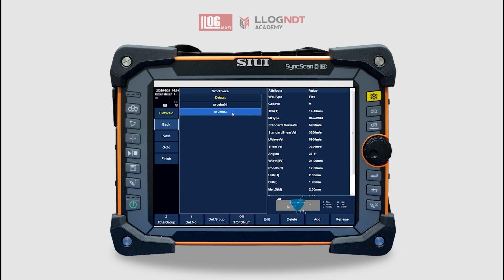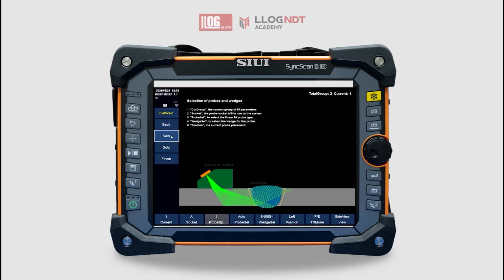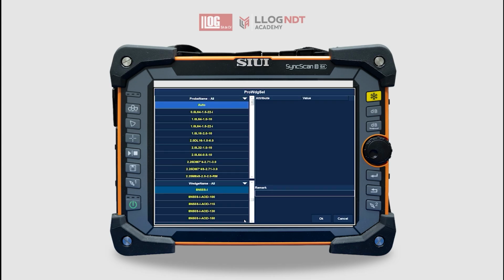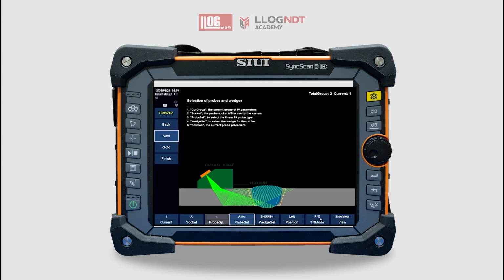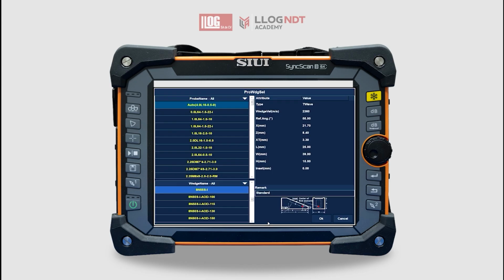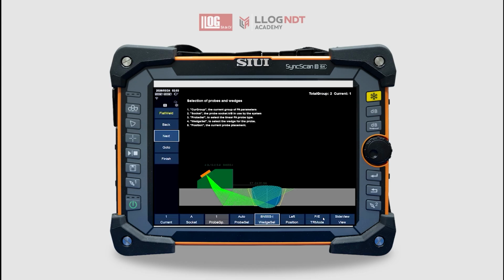To begin the scan plan, we select the number of groups to be used. In this example, we will configure 2 groups. For the first group, we select the transducer model, the wedge, define the transducer position on the left side, then press Next. Next, select shear waves, then press Next again.